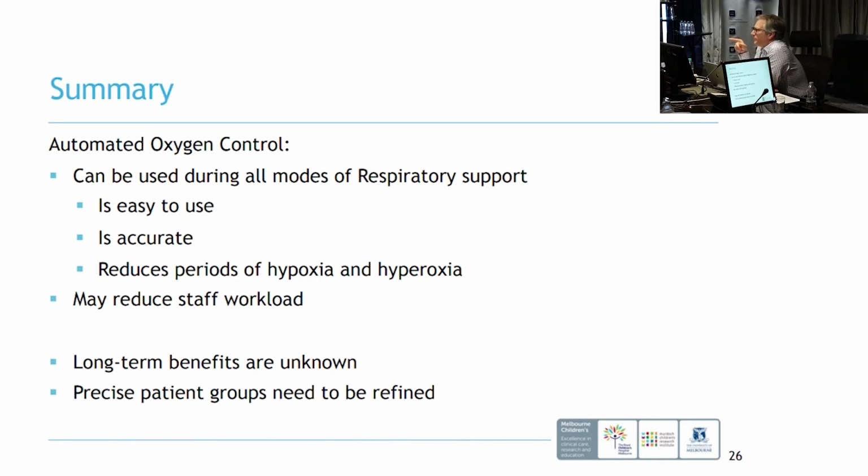It tends to turn up very quickly if you're at a low FiO2 as your reference and you suddenly desaturate. But yes, it can sometimes be slow to wean if you've gone from a low to a high, because it's saying you're a long way from the reference, so it's being more cautious. But that's the advantage of the adaptive and PIDs. They're meant to be more reactive to the different variabilities in the system than the old-fashioned ways.